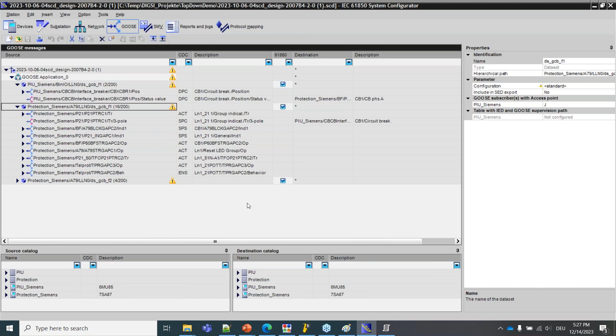So we can do either the import via that menu or using our 61850 station, selecting the file to be imported and selecting the file provided earlier by Yannick. I've already imported it earlier, so if I show that in our own system configuration tool, you can see that, for example, the GOOSE configuration has been imported. What is sent from the PIU, so the merging unit device, to the protection device, or what the protection device is sending back to the merging unit. So the import of the SCD is just a single click.